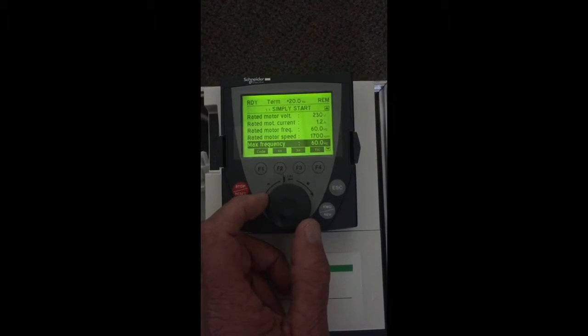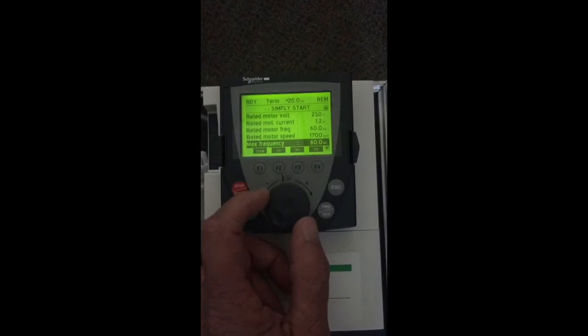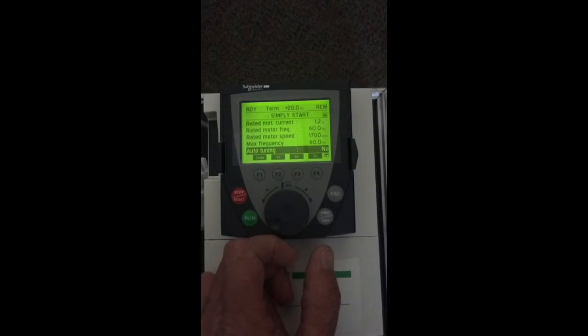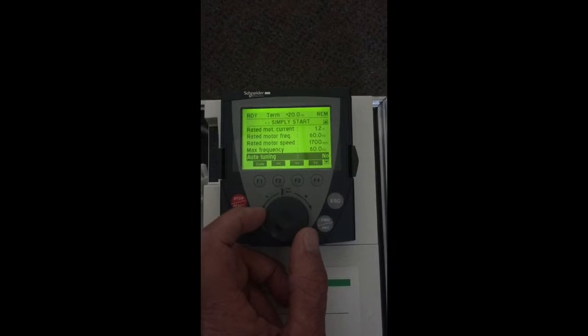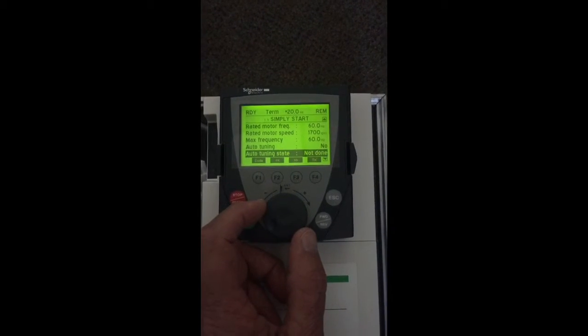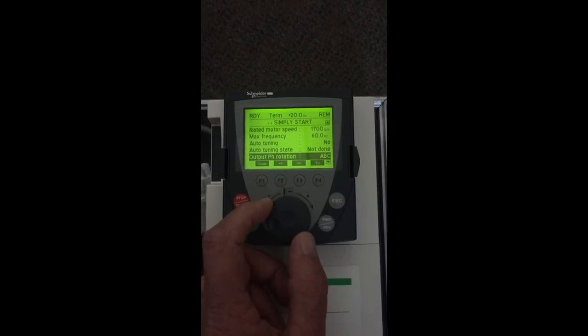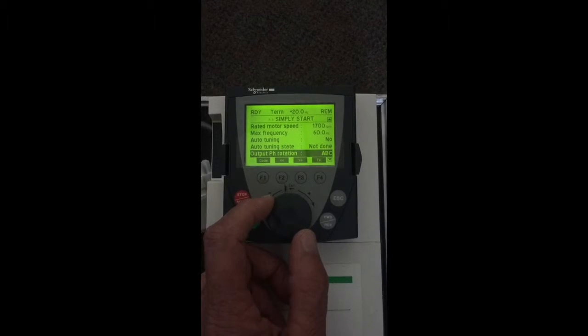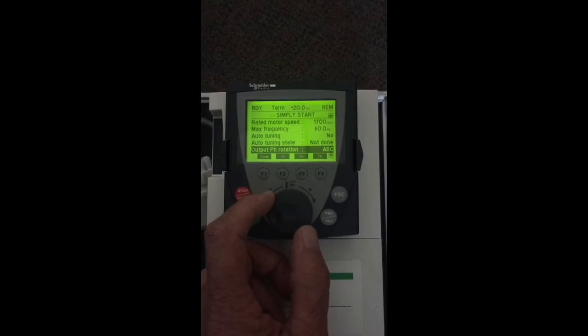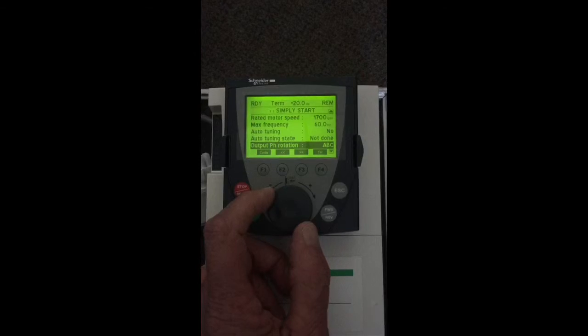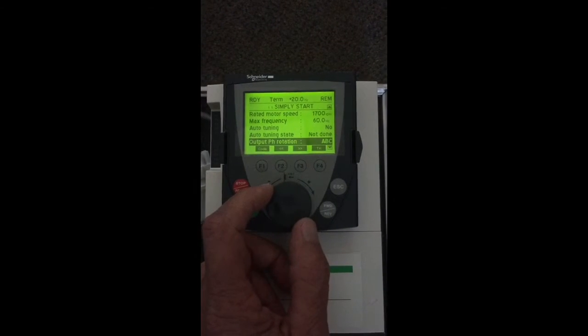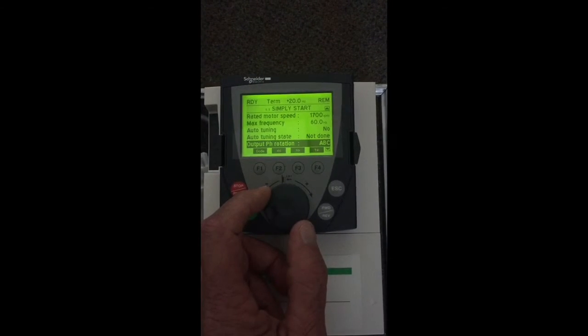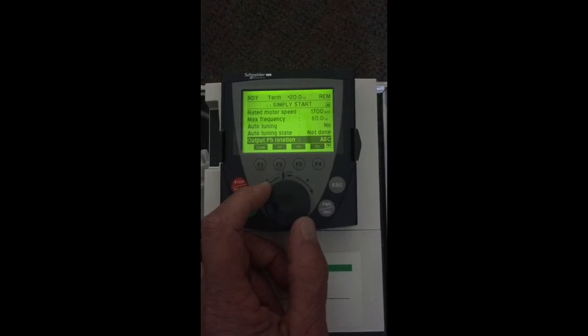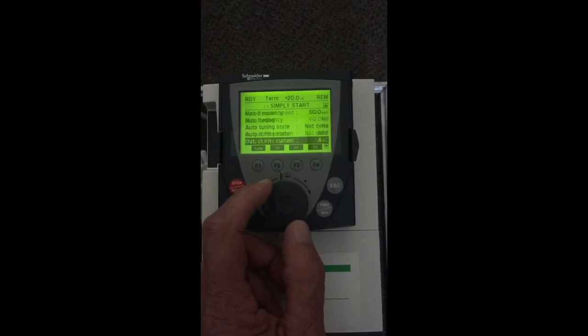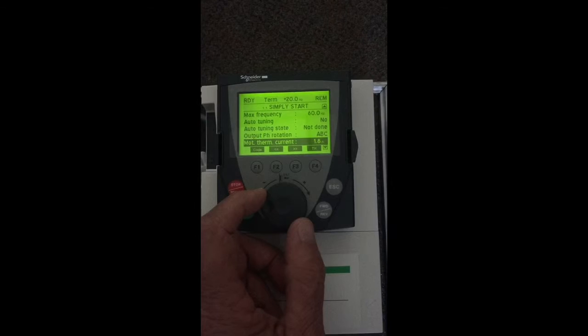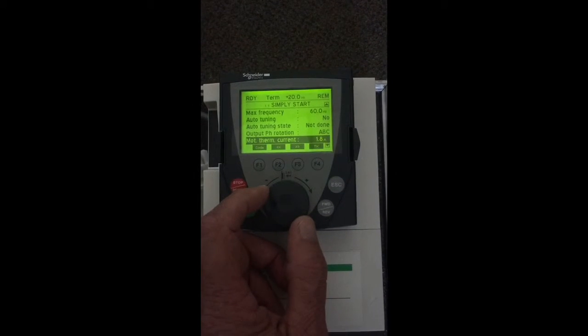Max frequency that the motor will ramp up to. We won't worry about auto tuning. Here's where you can adjust your rotation of your motor with the drive. I would correct the motor at the motor output terminals of the drive. I would not change this parameter. Motor thermal current.